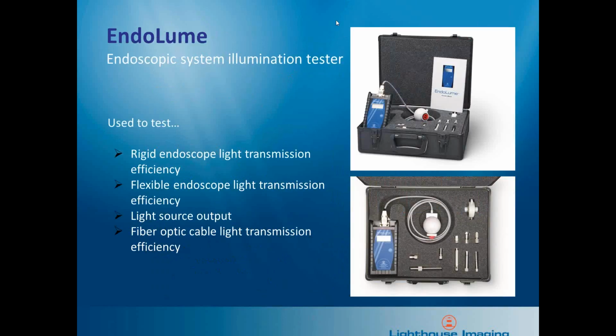So when we look at the EndoLume, again, it's an endoscopic system illumination tester. It tests strictly the illumination side components: light source, light cable, and endoscope. It will test the transmission efficiency of endoscopes, the light source output, and the light cable transmission efficiency.